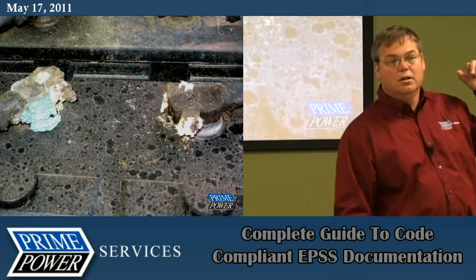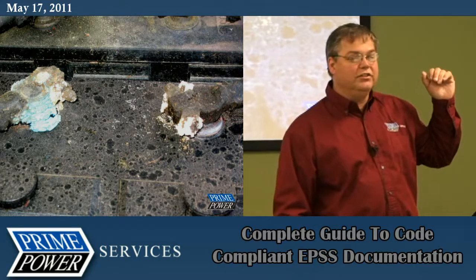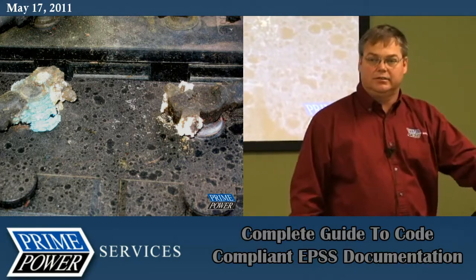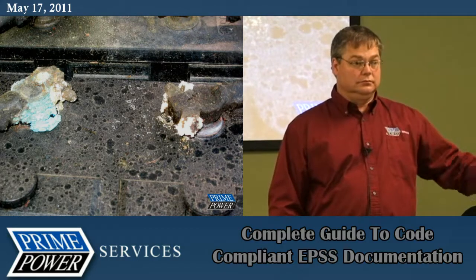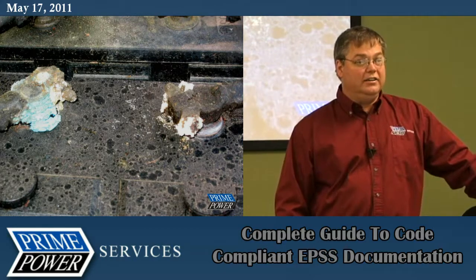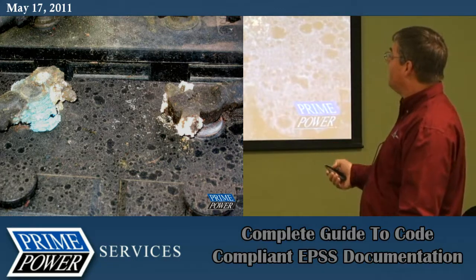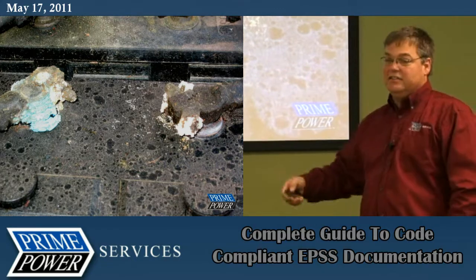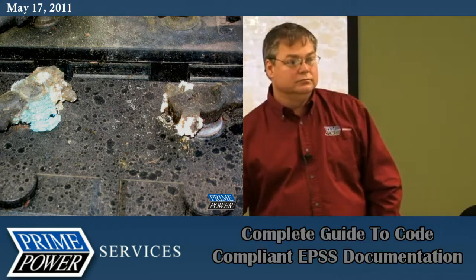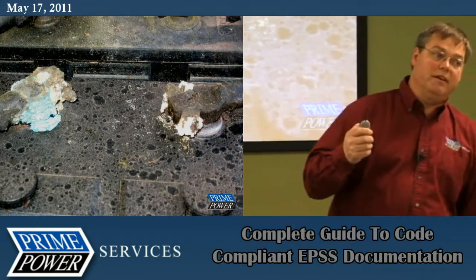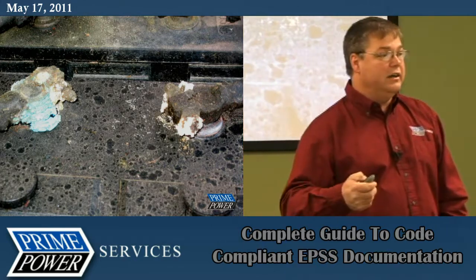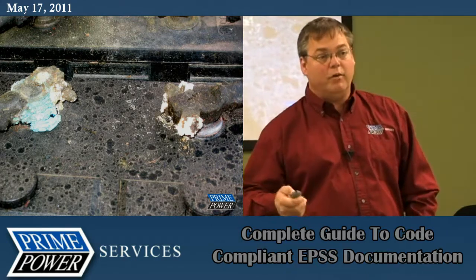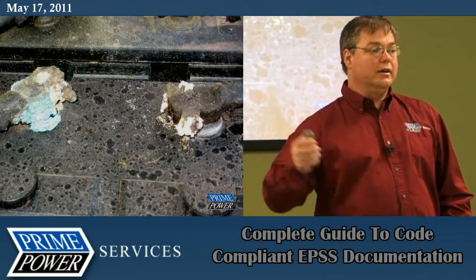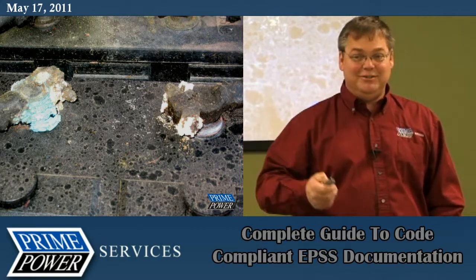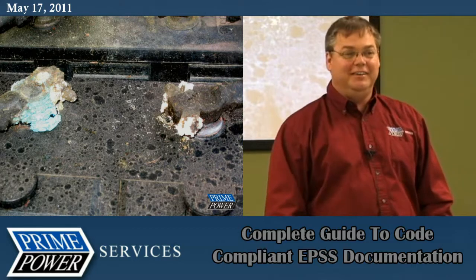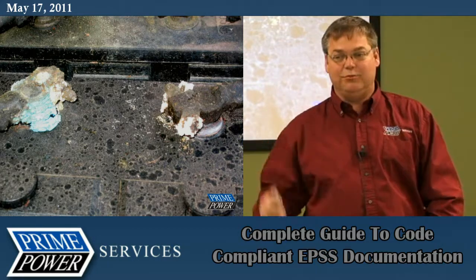That simple issue, I wouldn't say that's poor maintenance, I'd say that's lack of maintenance. That does happen. When you let a battery sit for a while, the only thing anybody did wrong was not taking care of it before it got that bad. A little grease on top would have helped prevent it a long time ago. But once it starts, it's going to grow, so you've got to stop what you're doing and take care of those things. Remember the gorilla? Some things you see every day, over and over, and they're just so obvious that they need to be fixed, and this is one of those type things.